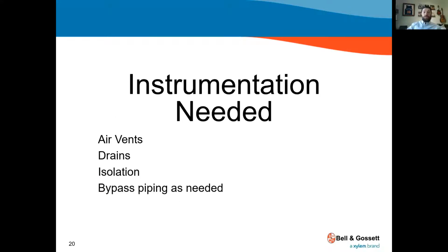So instrumentation needed on either end. You need air vents on both sides at the high point of your heat exchanger. Drains and isolation in case you need to get in this thing, turn it off, and also bypass piping is needed. A lot of these are seasonal, right? We might need to go around and make sure you put in your bypass piping where necessary.